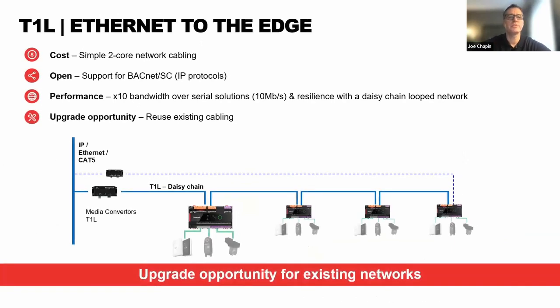This one here shows you how easy it is to simplify. Again, it's an open protocol. You get 10 times the bandwidth. You can upgrade, reuse existing cabling. The very top, the dash line, is indicating a long stretch using the adapter. Below that, you'll see the adapter. What it'll do is convert a category 5 to T1L via the adapter. Then it'll send it to each controller where you have 300 meters between each controller.